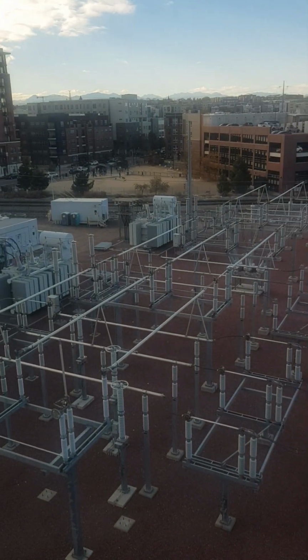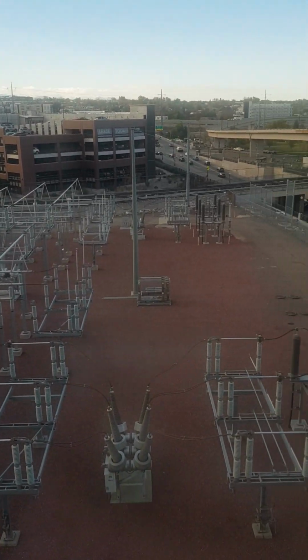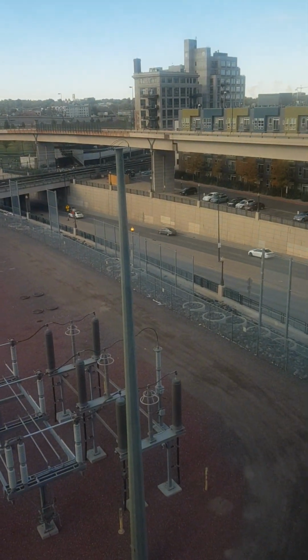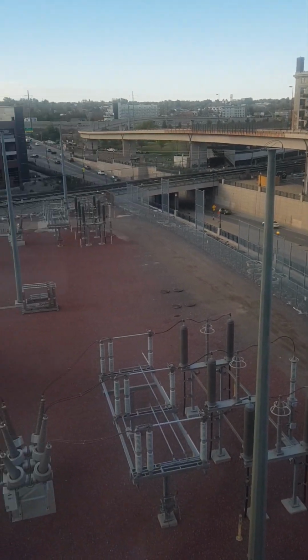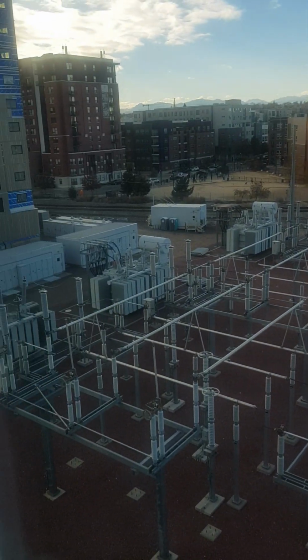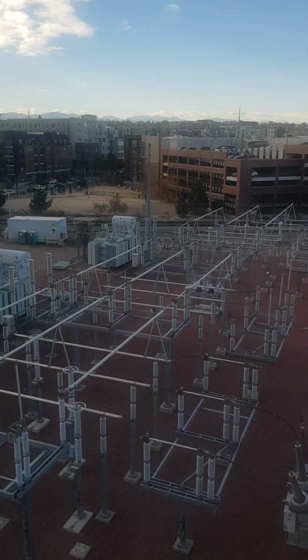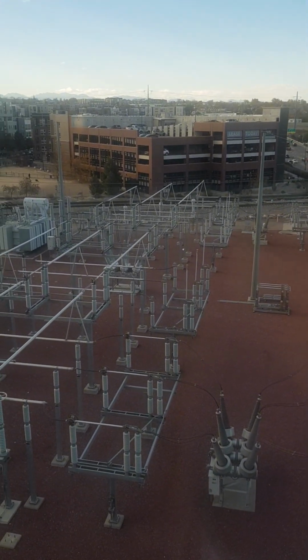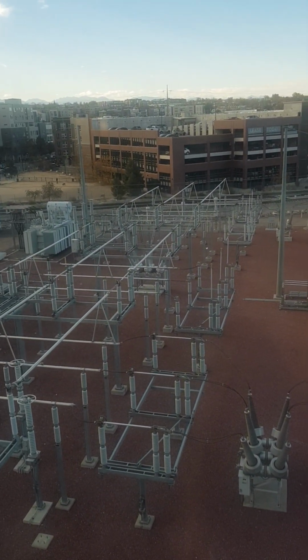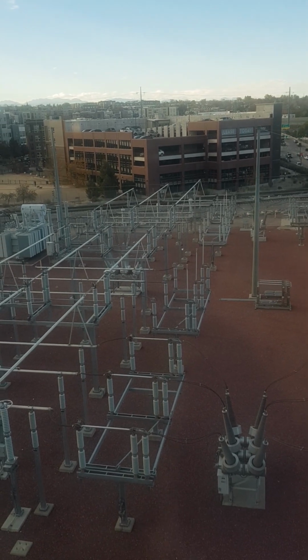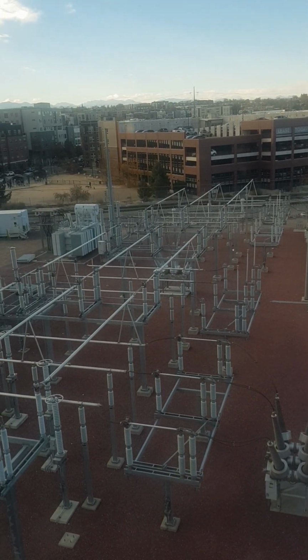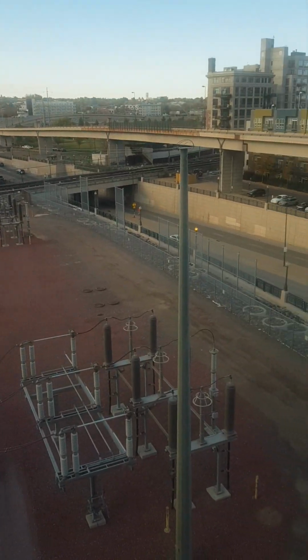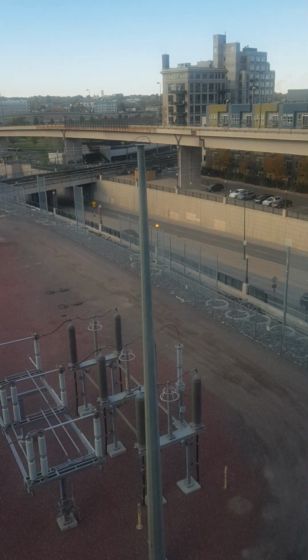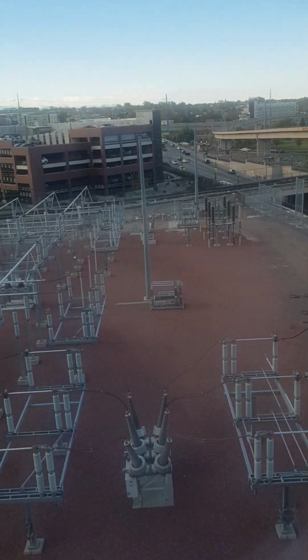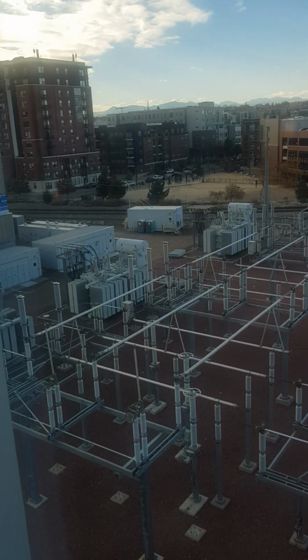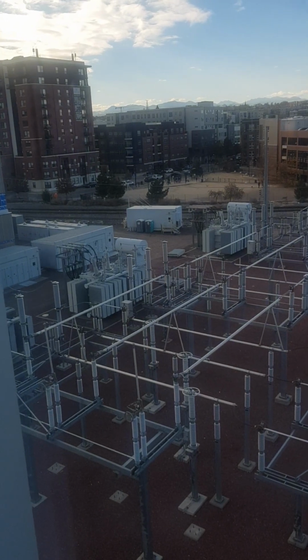This substation actually looks to me under construction. Okay, this is the incomer side. There is no high voltage line connected to it. And in the far end, there is the transformer to step down. As you may know, substations are used to step down the voltage from transmission or sub-transmission to the primary distribution level voltage. So from here, we could have 230 kV, 132 kV, and then at the output, you could have 69 kV or 33 kV, and so on and so forth, okay?